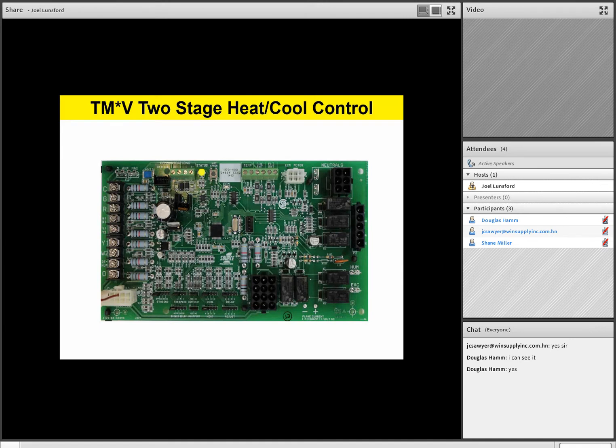It's a great product. So as we take a look at our left-hand side of the board, let's talk a little bit about our low voltage wiring, and then we'll talk about how to set the board up, and then we'll answer any final questions or comments you might have on the ECM motor products. But at this time, let's go ahead and cover our low voltage wiring as we have a tour of the board, if you will, as we take a look at all the components and the layout of this board as well. So starting out on the left-hand side, we have a 24 volt common on our low voltage terminal. This board, again, is very, very versatile. This furnace is very versatile. You can hook it up to a standard 24 volt system, or you can go with our 4-wire communicating system.